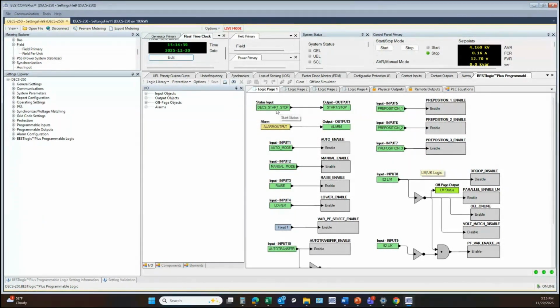As you can see, when the DECS is in a started state, it will trigger output 1. If any alarms occur, it's going to trigger output 3. Input 1 is being used to enable the auto mode, and input 2 is being used to enable the manual mode. Raise and lowers are being used for inputs 3 and 4. Those will raise and lower the set points of your active mode of operation. So if you're in AVR control, it'll raise the AVR set point. Prepositions up in the right, we have various inputs triggering those prepositions.